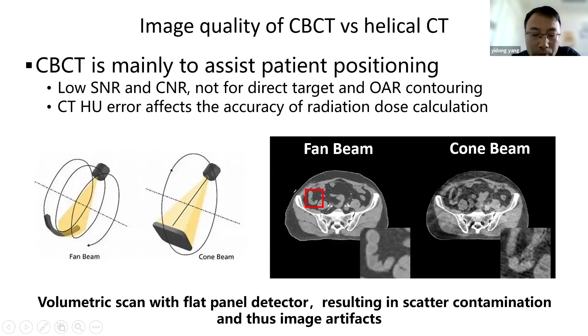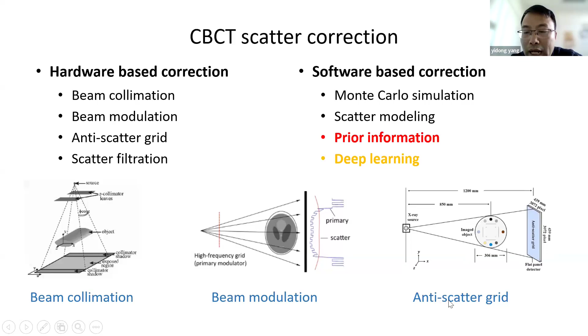So my research focuses on improving the image quality of cone beam CT. There are many methods to reduce cone beam CT scatter, based on hardware and based on software. We focus on using prior information from planning CT, and we also develop deep learning methods to improve the image quality. We also design some hardware to reduce the scatter. There are different ways of reducing scatter: beam collimation, beam modulation, and this one we may be familiar with, the anti-scatter grid.